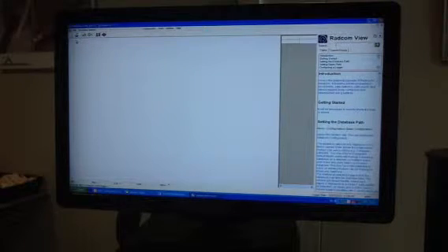On the top left hand side you have a series of tabs and one of them says Configure Logger Wizard. Click on Configure Logger Wizard and it will bring up the actual screen for the logger type. There's two ways you can look at this. You can auto detect your logger, or you can select the logger from the drop down box. As we are doing a multi-log GPRS logger, we will select multi-log GPRS.